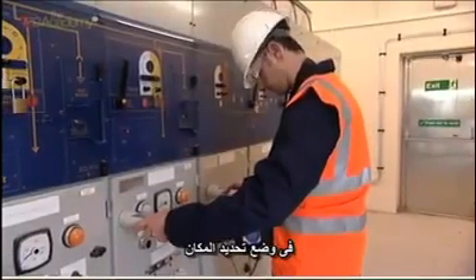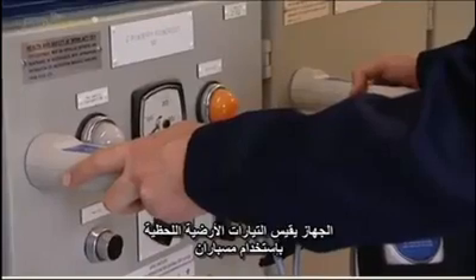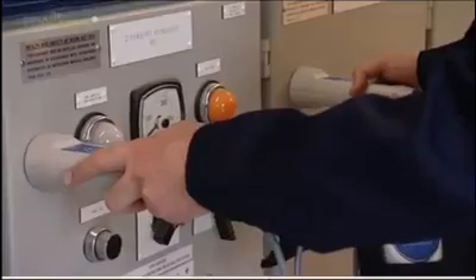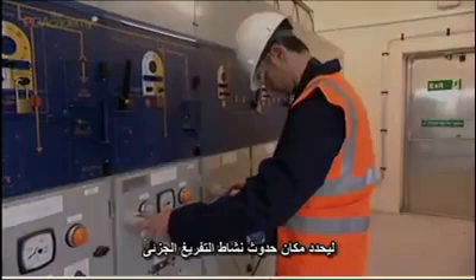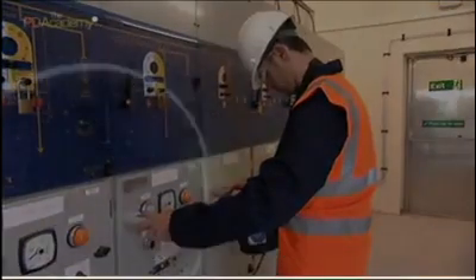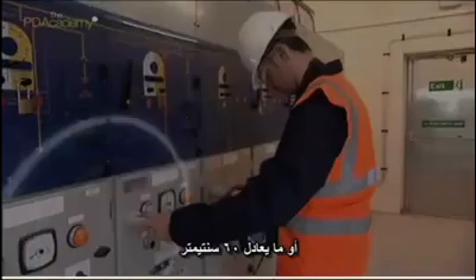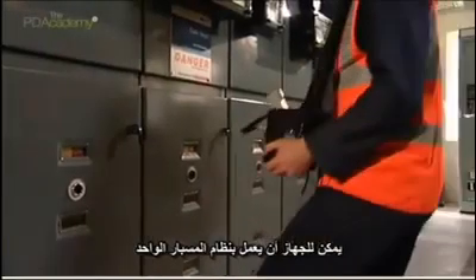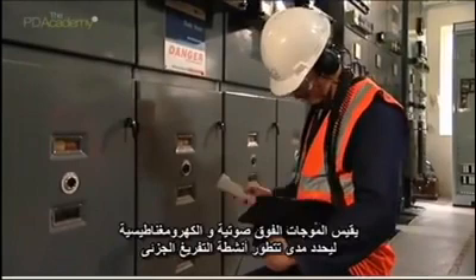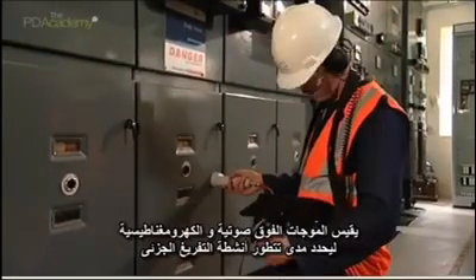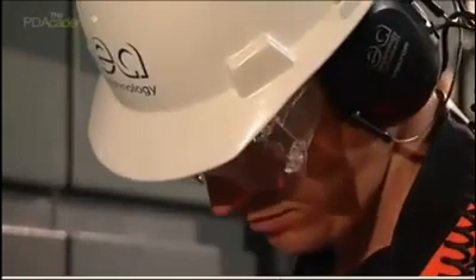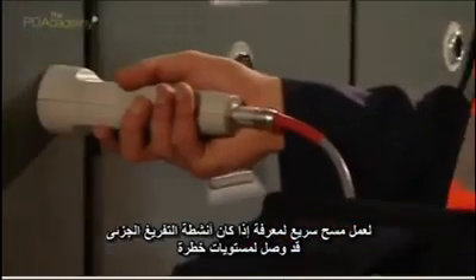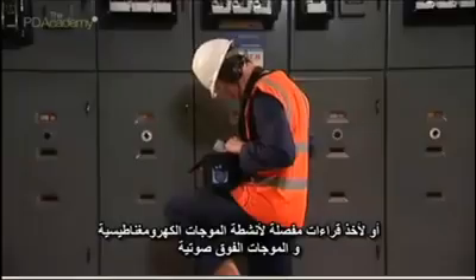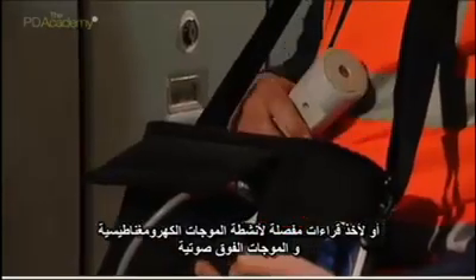In location mode, the system measures transient earth voltages using two probes. The instrument measures time of flight differences to locate the position of the PD activity to an accuracy of 2 nanoseconds, equivalent to 60 centimeters. You can also use the system in single probe mode. This measures both ultrasonic and TEV discharges to determine the severity of the PD activity. Options include using factory threshold settings for a quick survey to determine whether PD activity is at critical levels, or taking detailed readings of ultrasonic and TEV activity.